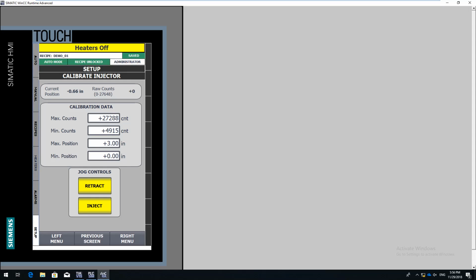One of the things we'll see on both screens is what the current position might be. So this is the analog signal back from the linear pot, and we've scaled this to inches instead of the raw counts. So at the top here we do have raw counts. So our 0 to 10 volt signal has been converted, comes in as 0 to 27,648 counts. Currently we're reading nothing. Due to the scaling of the system, it's saying 0 would happen to be 0.66 inches in the negative direction.